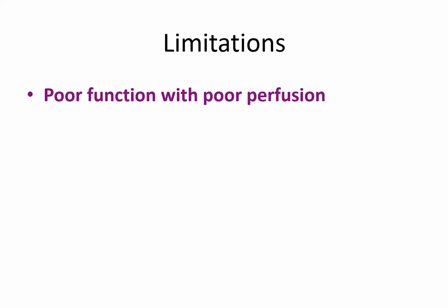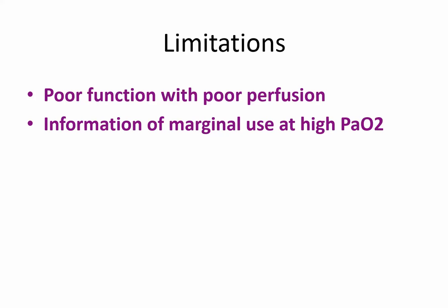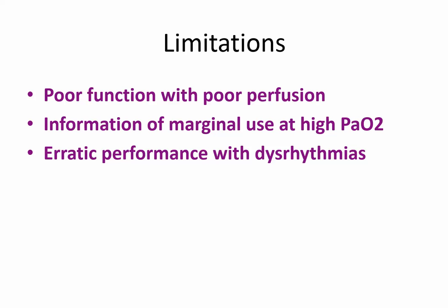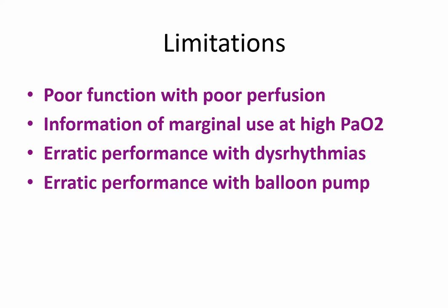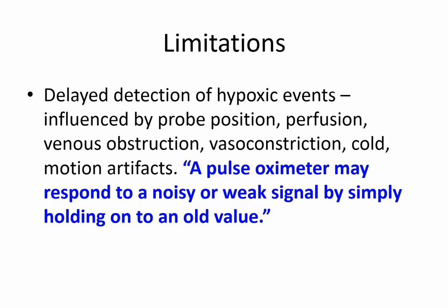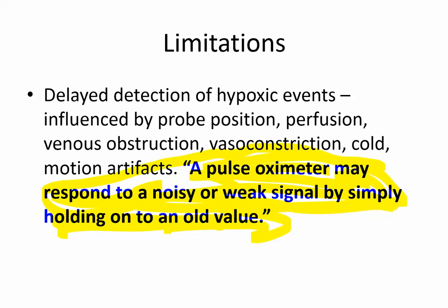It's got poor function with poor perfusion. It's of marginal use with a high arterial partial pressure of oxygen. It provides erratic performance with dysrhythmias and with a balloon pump. Again, I can't emphasize this enough. The pulse oximeter may respond to a weak or noisy signal by holding on to the old value. That's a significant problem if you don't know that that's what's happening. You can end up with a significant problem because you think the patient's oxygenated adequately, and in fact the problem is that the pulse oximeter simply quit working.